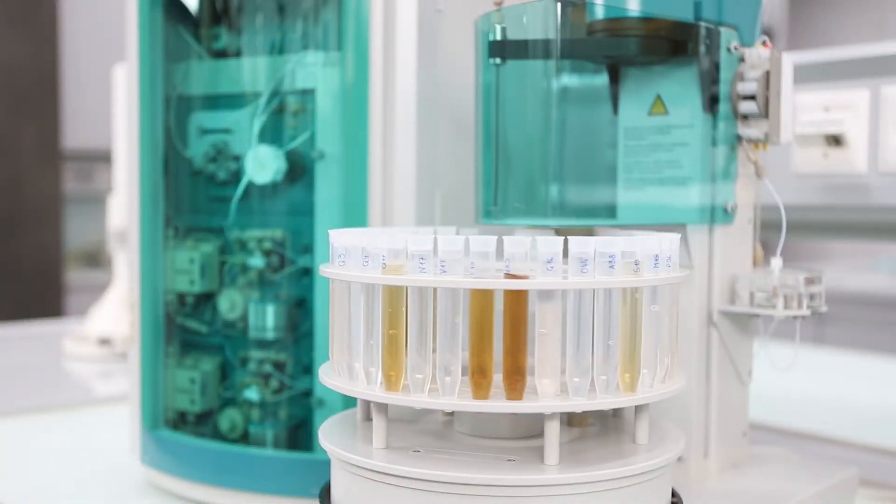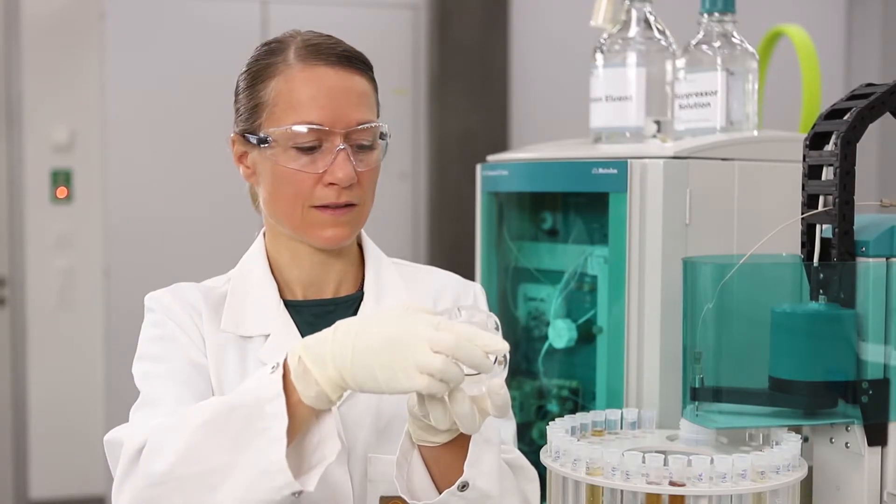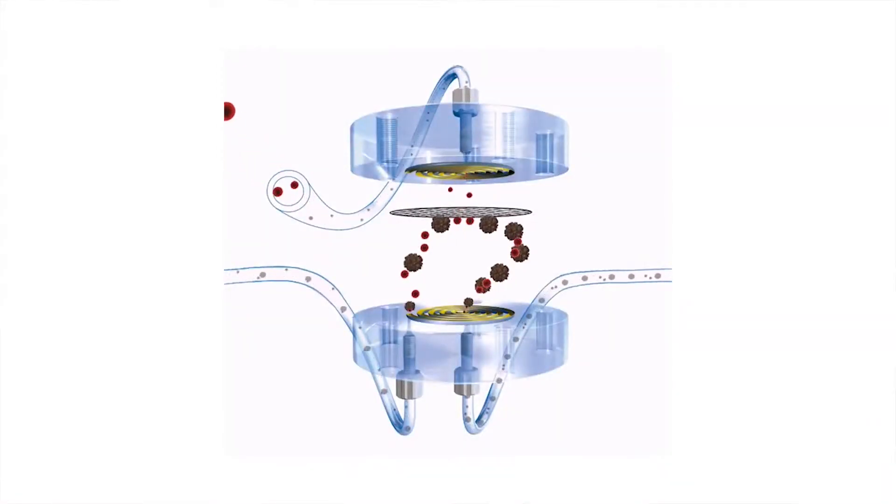From the sample processor, the sample automatically passes the ultrafiltration cell before being injected onto the column. When the sample flows past the filtration membrane, a part of it is filtered. After the filtration, the membrane is flushed from both sides so that no filter cake is formed and the membrane can be reused.